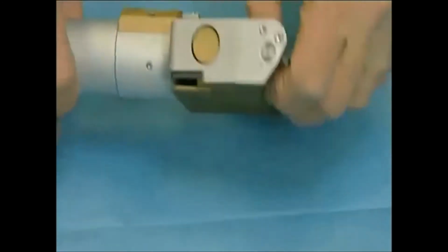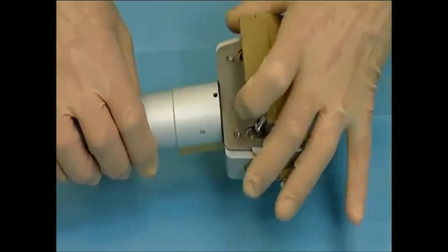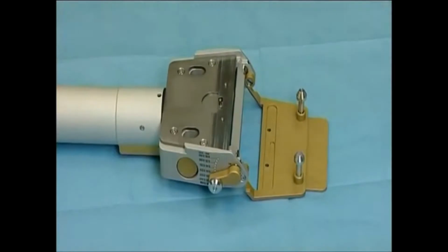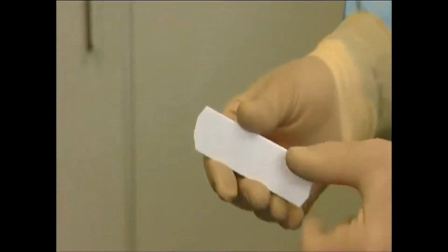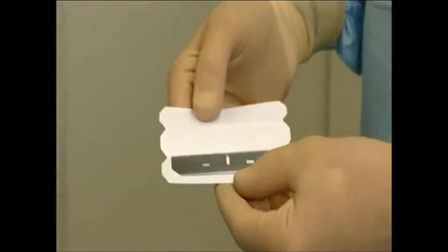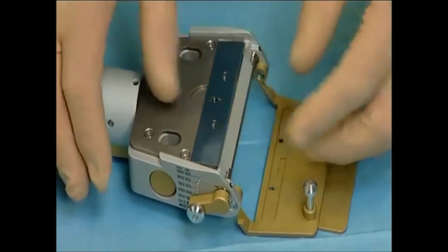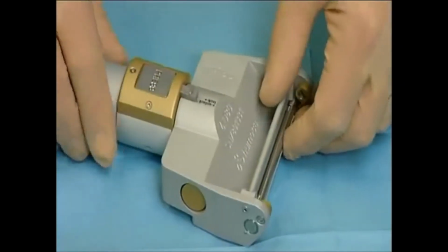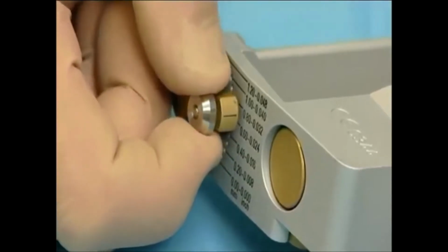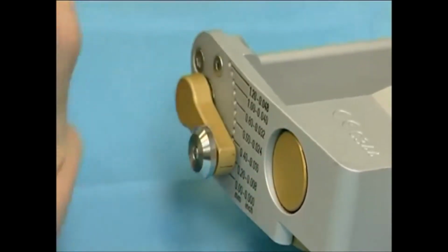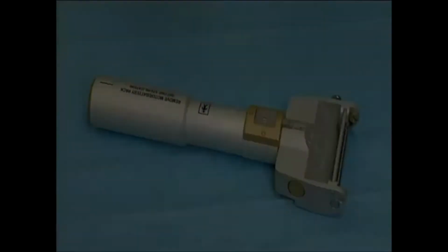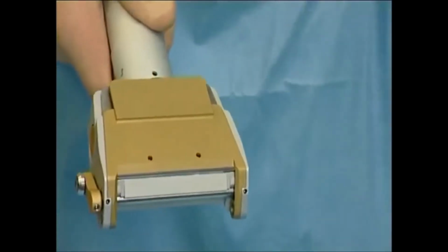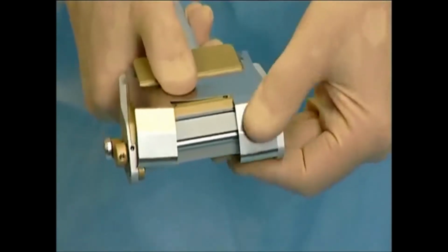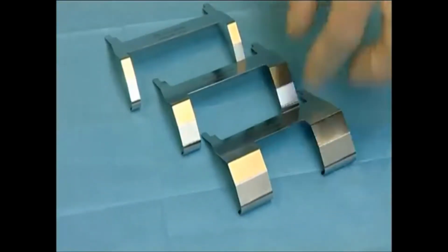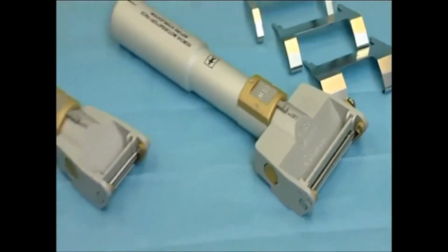To insert a blade in the dermatome, the 2 locking buttons of the head are pressed and the blade cover is opened, thus offering access to the blade compartment. The Humeca dermatome blade is precision ground in a double facet shape for minimum resistance and smooth cutting. The blade is put in place and the cover is closed. The graft thickness is adjusted by means of an adjusting lever fixed at predetermined positions to prevent accidental change. The dermatome can be provided with a width-reducing clamp to limit the cutting width. Several clamps are available for both the D42 and the D80 dermatome.